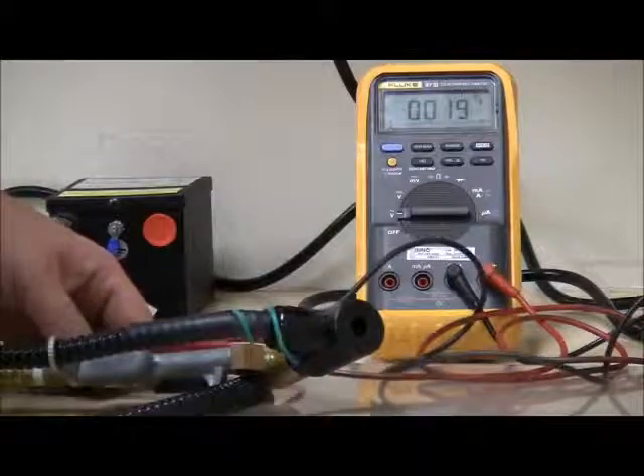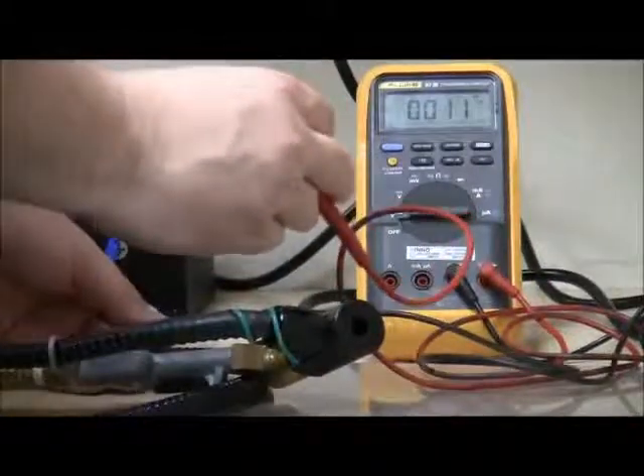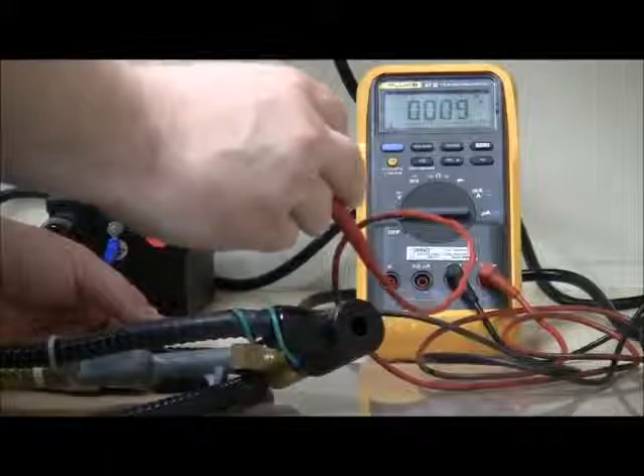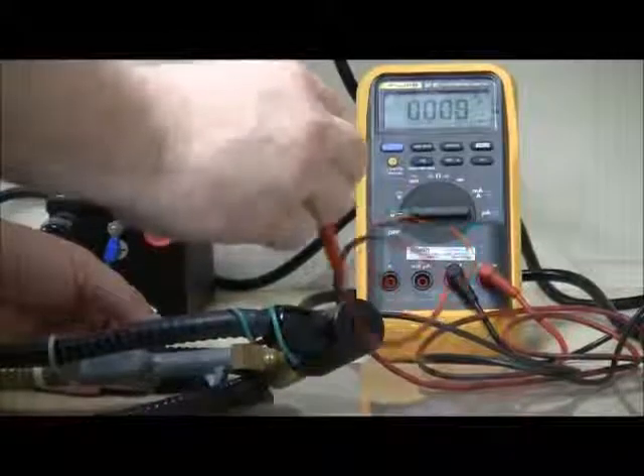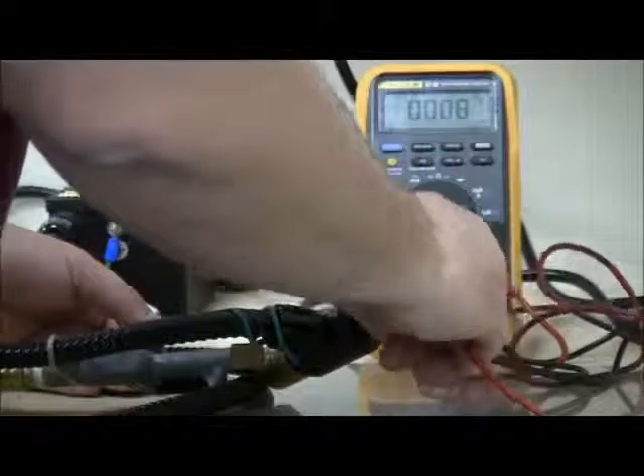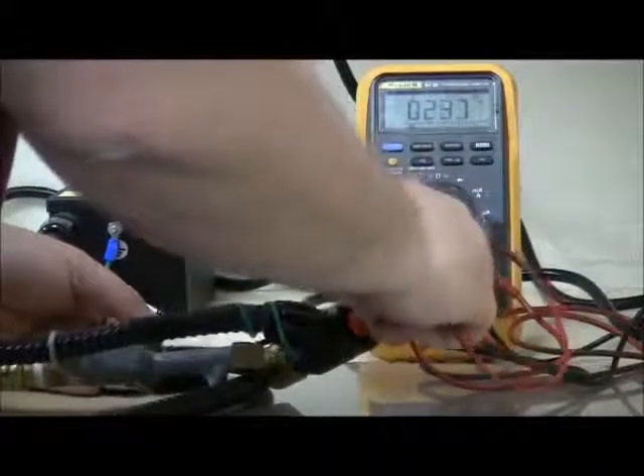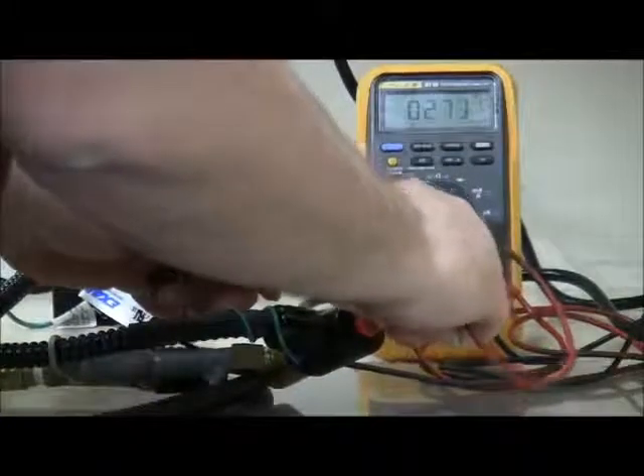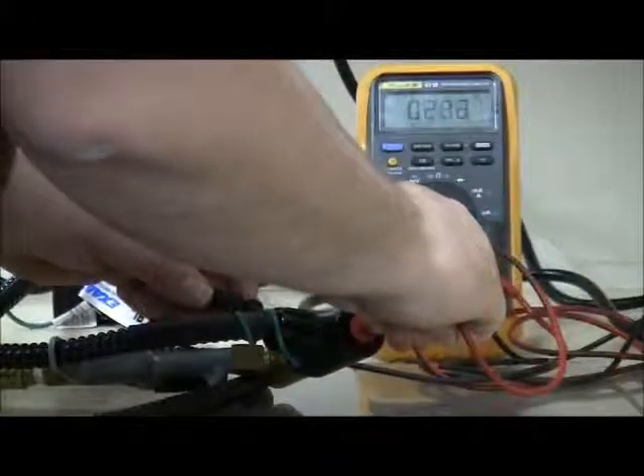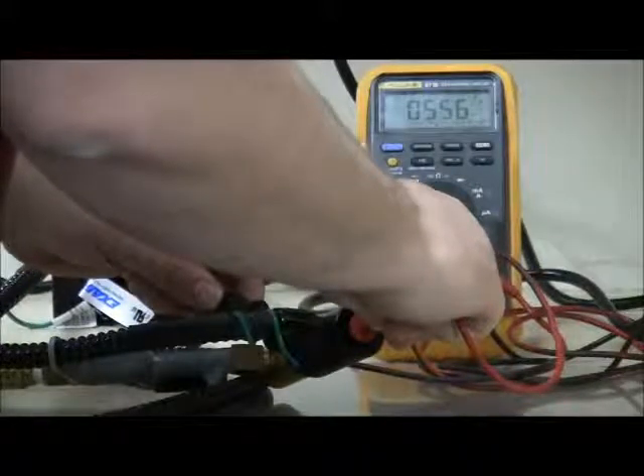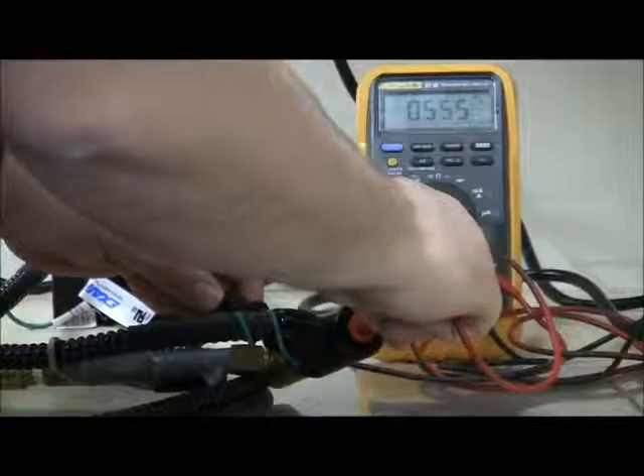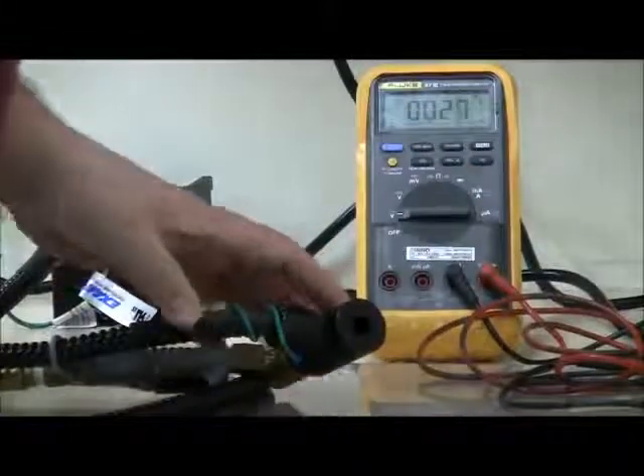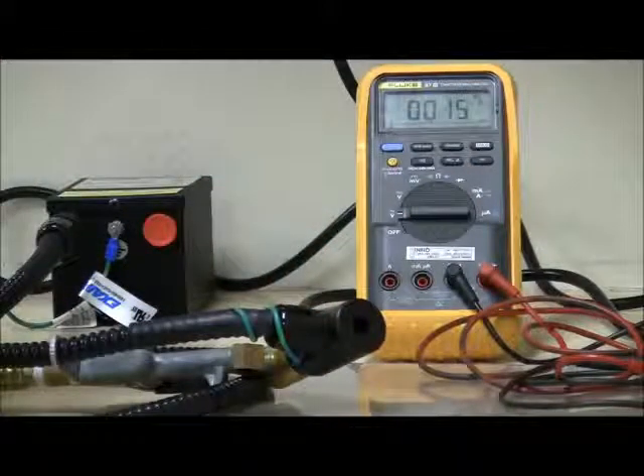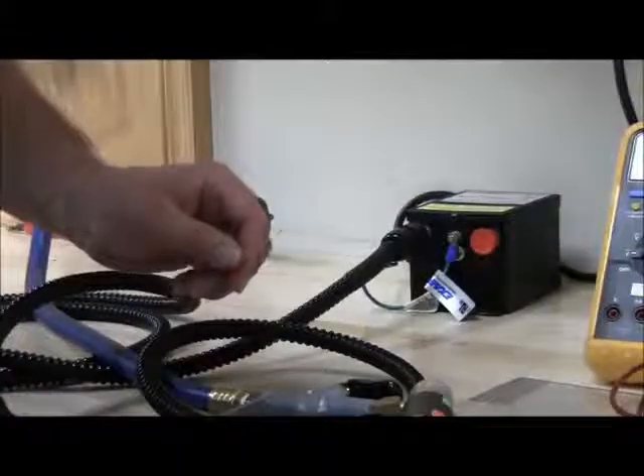So we're going to check the voltage from the emitter point to the ground. Now we're looking for 510 to 580 volts AC, so if your meter's voltage settings have a range, select the appropriate one. Then place one probe on the emitter point, which is found inside the ion air gun, and one probe on the ground. As we can see, we're measuring 556 volts AC. We're well within specification. Again, I'm using an ion air gun, but the ion air jet, ion air cannon, and ionizing points are all similarly tested. Now we'll move on to cleaning.